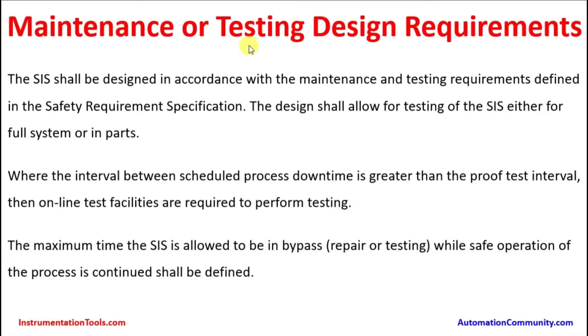Maintenance or testing design requirements: the safety instrumented system shall be designed in accordance with maintenance and testing requirements defined in the safety requirement specification. The design shall allow for testing of the SIS test facilities either for the full system or in parts. Where the interval between scheduled process downtime is greater than the proof test interval, online test facilities are required to perform testing.